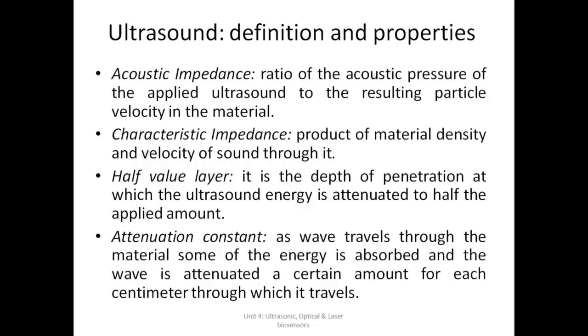Then we have an important term called half value layer. This is the depth of penetration at which the ultrasound energy is attenuated to half the applied amount. For example, if I applied an ultrasound of magnitude X, but when it traveled 2 centimeters, the magnitude that was left was X by 2, then 2 centimeters will be called the half value layer for that particular medium.